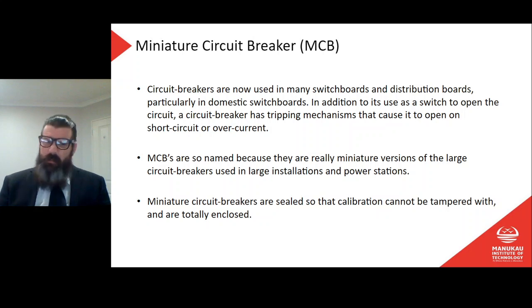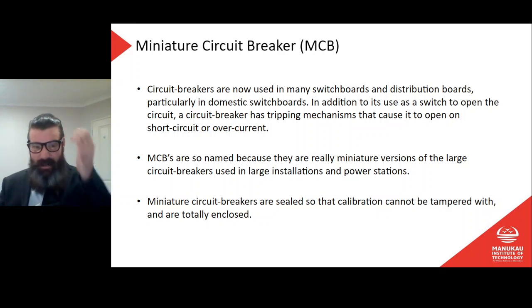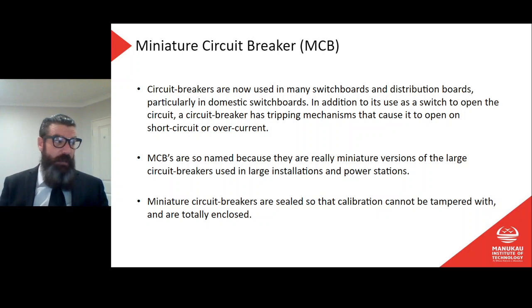Most commercial buildings will be circuit breakers in the switchboards. When we start getting to large industrial factories, warehouses, that kind of thing, then we're starting to see the HRCs, right? Because our short circuit currents become higher. But certainly, even in industrial, commercial settings, within offices, for lighting and normal power points and that sort of stuff, that's all still generally controlled by circuit breakers. Really easy to reset, right? So it trips, I can go and reset it, and a little bit easier to use as an isolator.